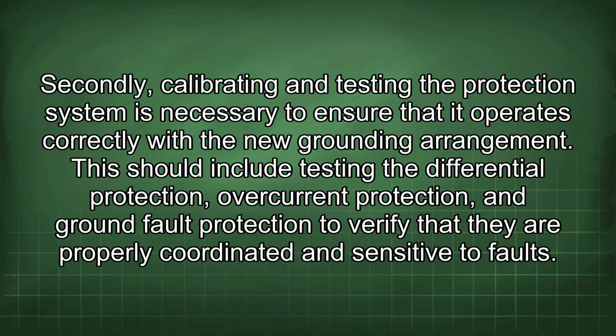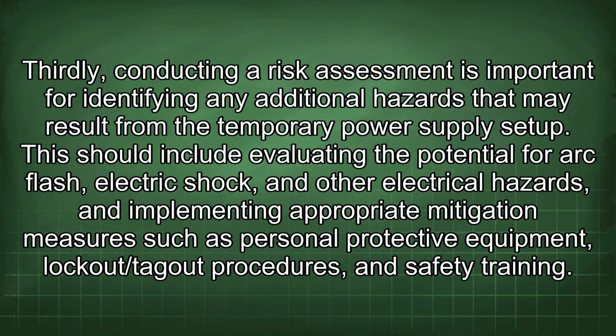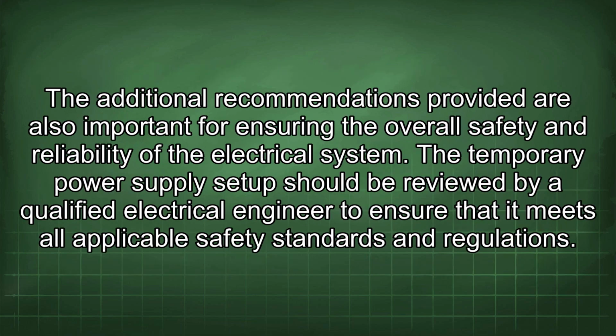Secondly, calibrating and testing the protection system is necessary to ensure that it operates correctly with the new grounding arrangement. This should include testing the differential protection, overcurrent protection, and ground fault protection to verify that they are properly coordinated and sensitive to faults. Thirdly, conducting a risk assessment is important for identifying any additional hazards that may result from the temporary power supply setup. This should include evaluating the potential for arc flash, electric shock, and other electrical hazards, and implementing appropriate mitigation measures such as personal protective equipment, lockout/tagout procedures, and safety training. The additional recommendations provided are also important for ensuring the overall safety and reliability of the electrical system.